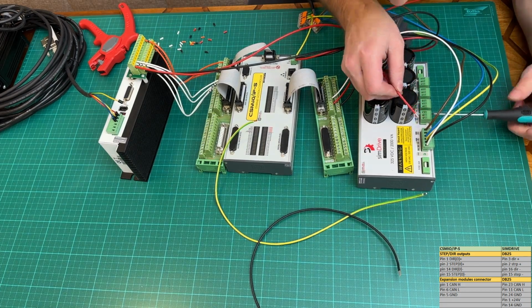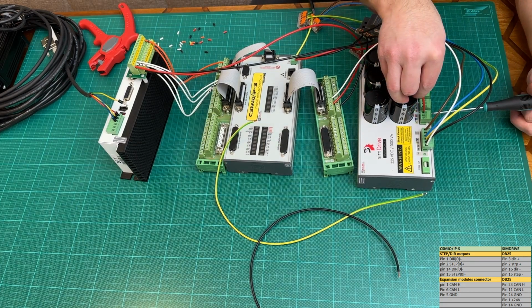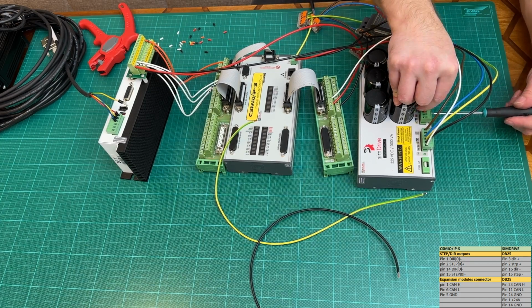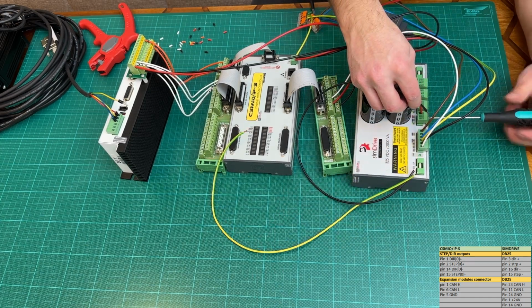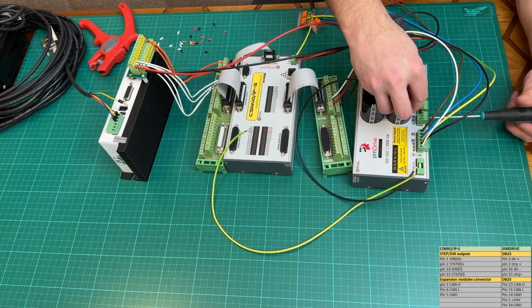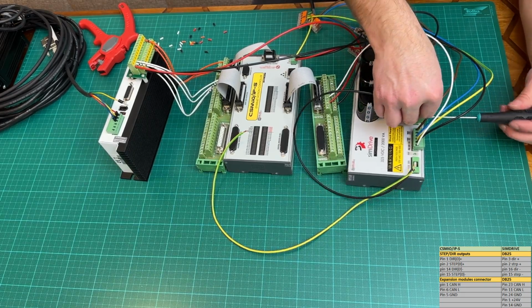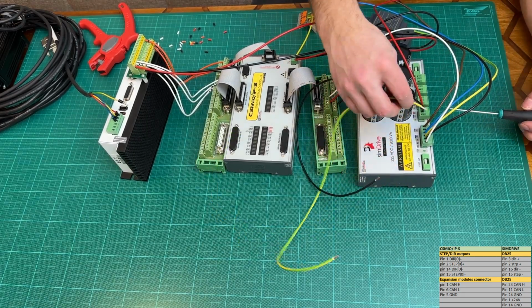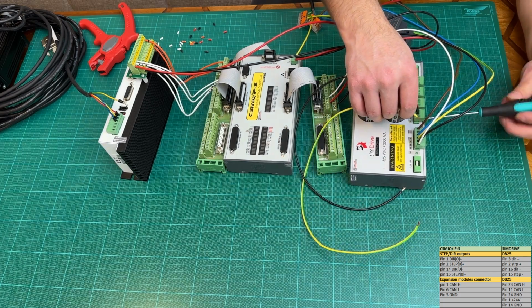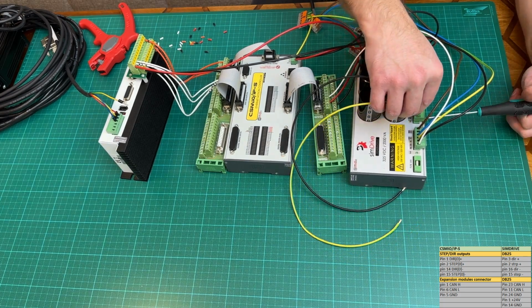And now the only thing remaining to do is connect the servo motor main power from the power supply to the servo drive. Be sure all things are powered off because the power module contains high capacity capacitors, which remain charged after AC power disconnection even for 5 minutes.